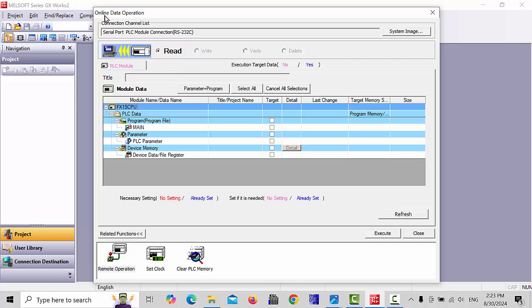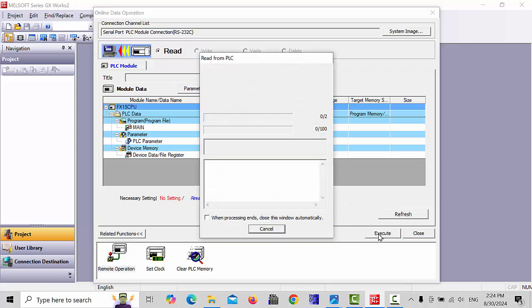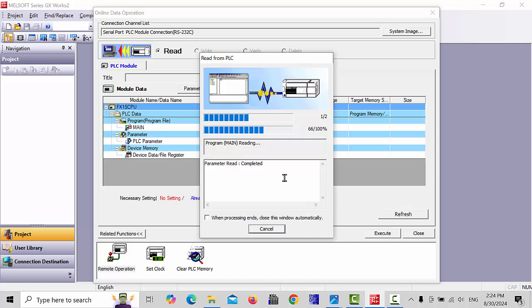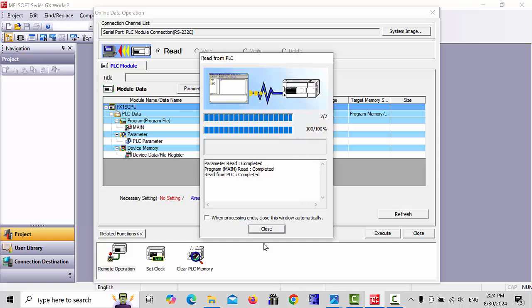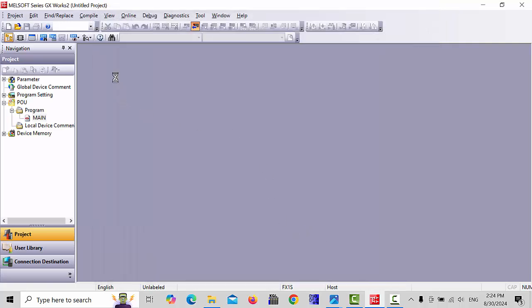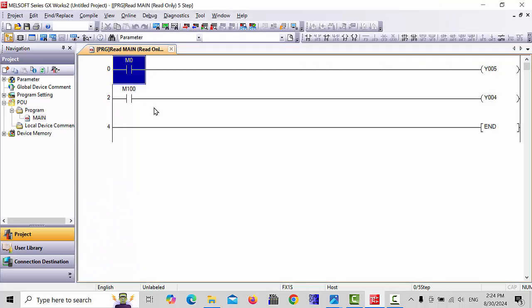This page will appear and here you have to read the program from the PLC. Select which you'd like to read, click on Parameter plus Program or Select All, then go to Execute. The program will be uploading from the PLC. When completed 100%, close this dialog and close this page. The program inside the PLC will appear on the main page.